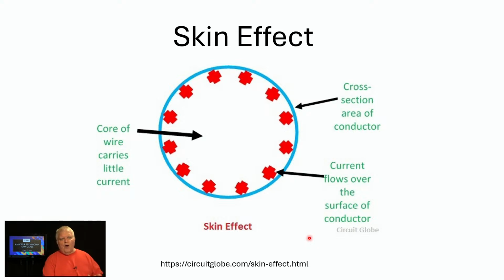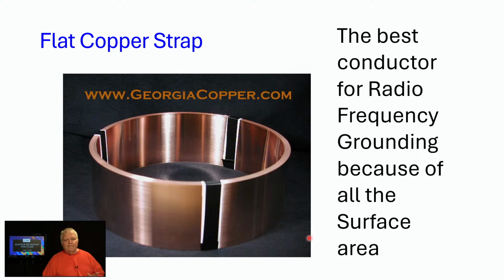which is one of the reasons why we say that the best grounding conductor is flat copper strap, because it has a lot of surface area. And so radio frequency current easily passes on the sides of flat copper strap. And so it has very low inductance, and it's the best thing you can get for grounding.